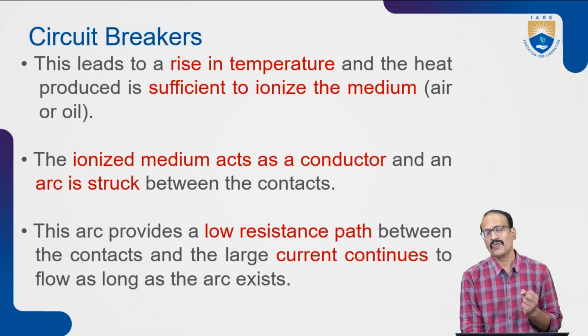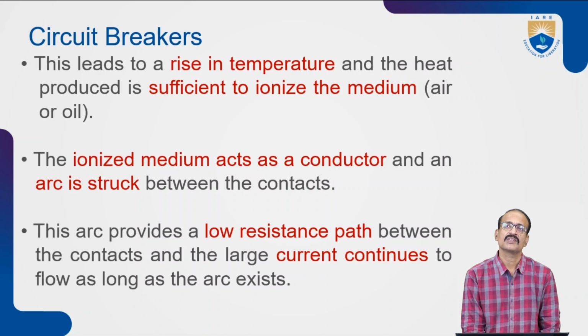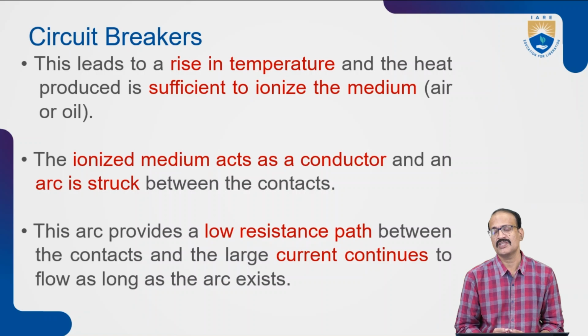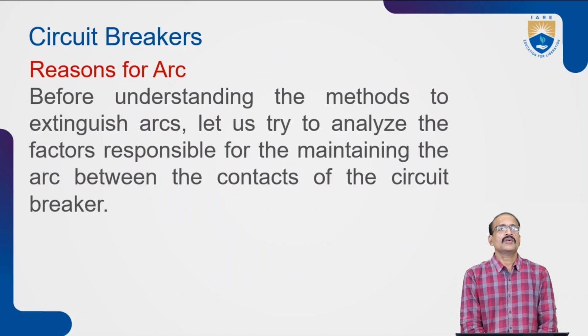So this arc provides a low resistive path, and this arc continues, and the current supply and transmission continue, and the large current continues to flow as long as the arc exists. So even though you have separated the contacts, the arc has given the supply a low resistance path to continue, which is spoiling the purpose of circuit breaking. So what is the reason for the arc?